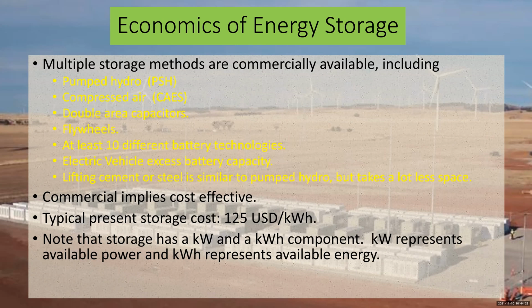Now, one thing we need to recognize with storage is that there's a kilowatt and a kilowatt hour component—power and energy. Both are important, because when you turn on your electric dryer, you need 5,500 watts right away to heat it up. But if you run it for an hour, it's not going to stay at 5,500 watts the whole time—it might use 1 or 2 kilowatt hours over that time. So kilowatts and kilowatt hours are both important factors describing storage.